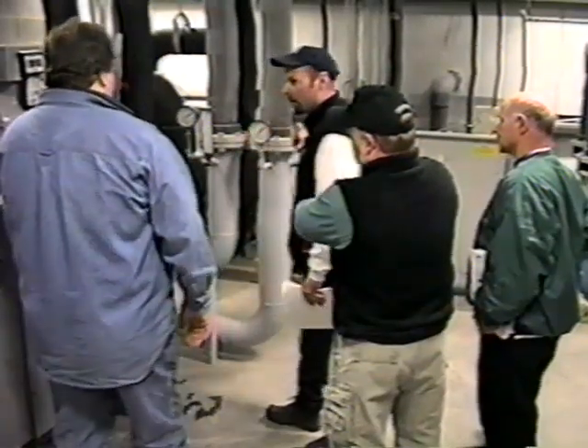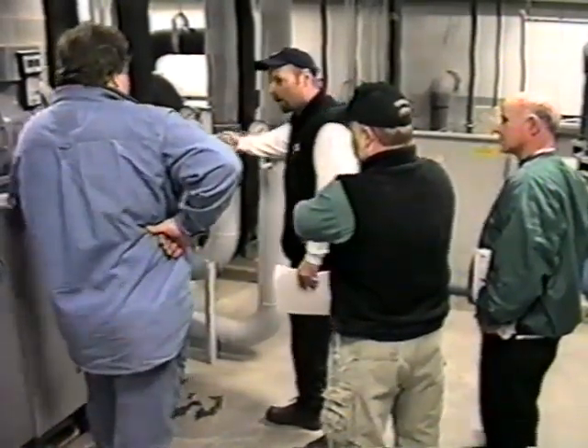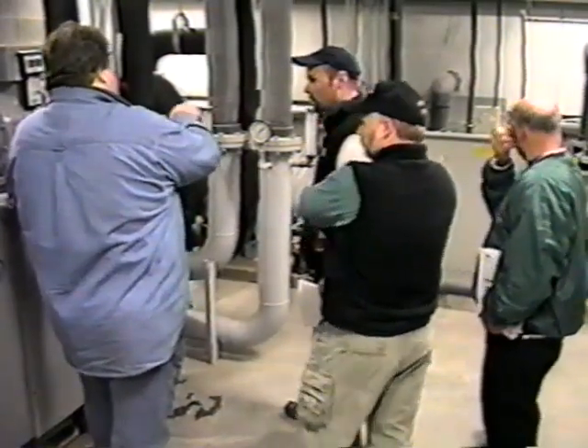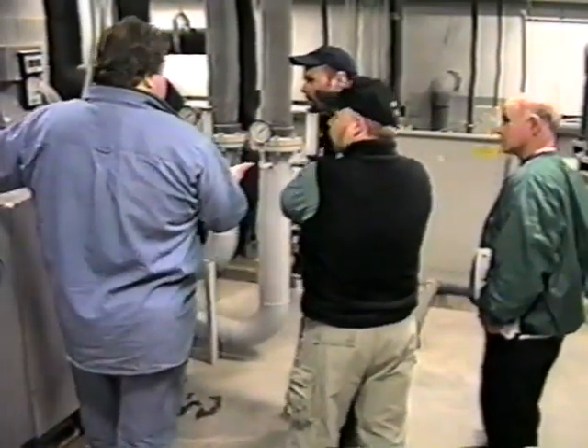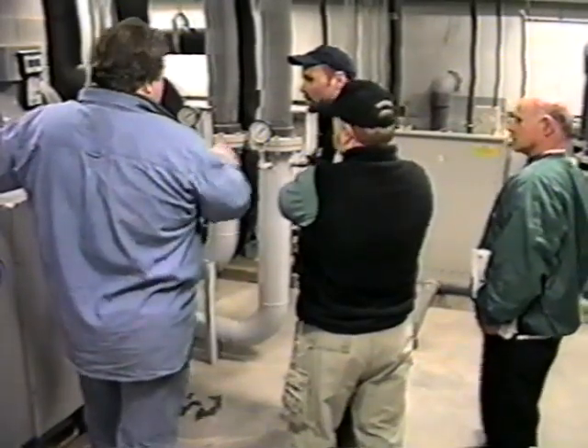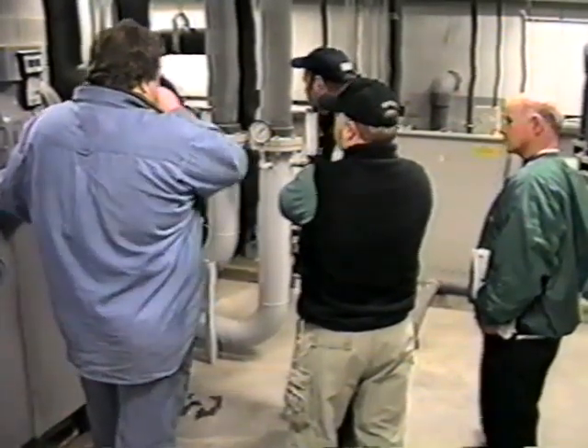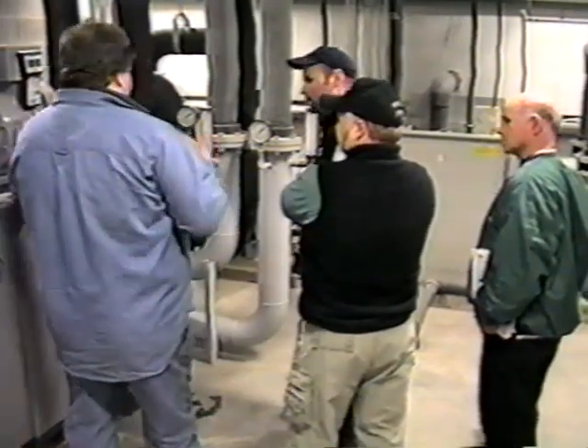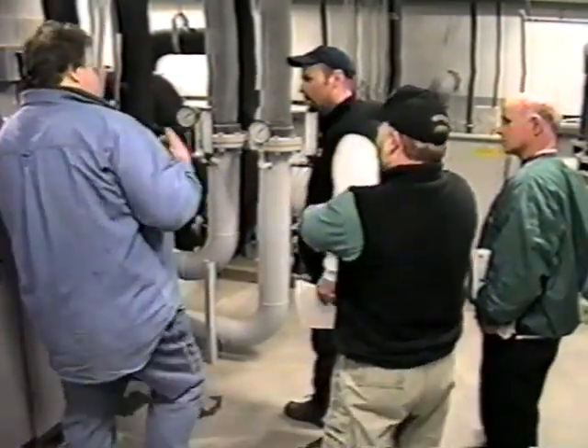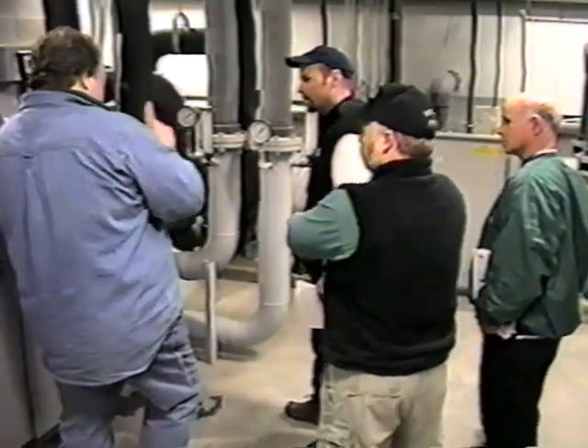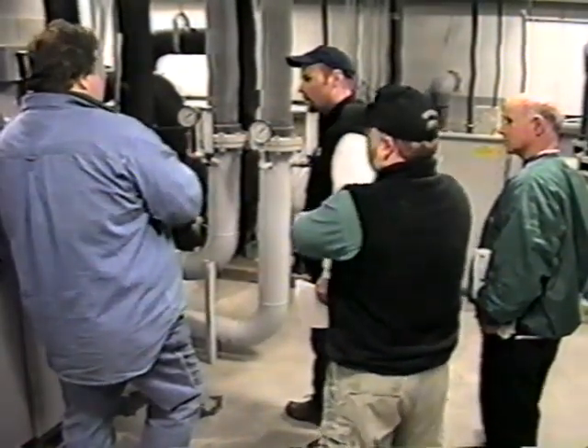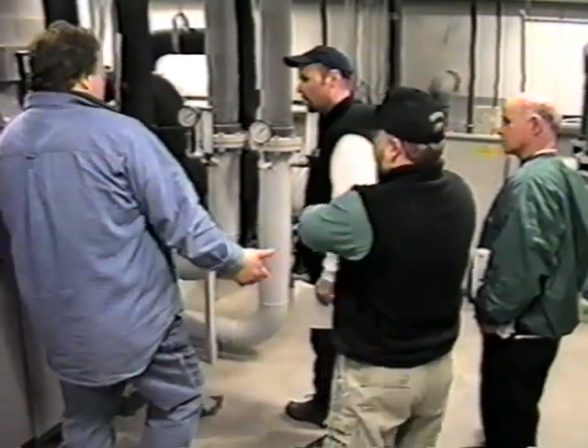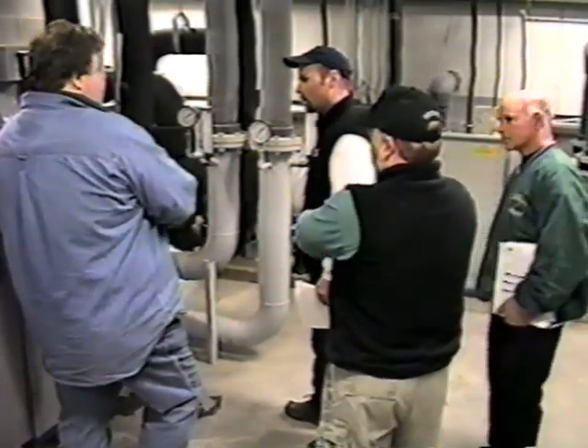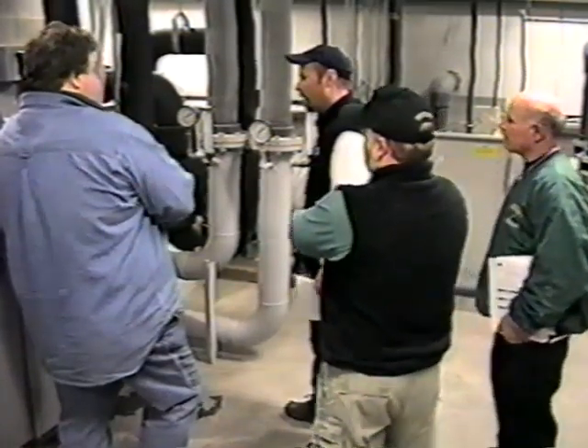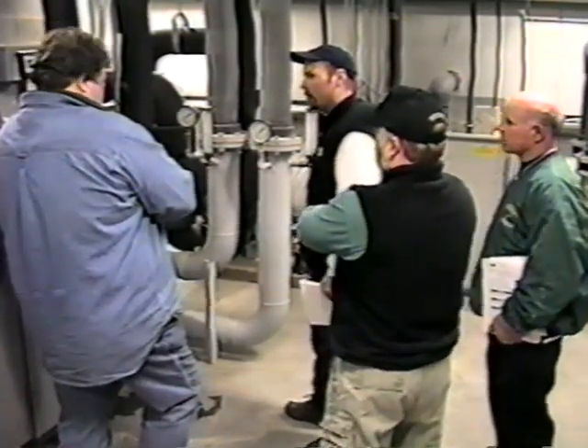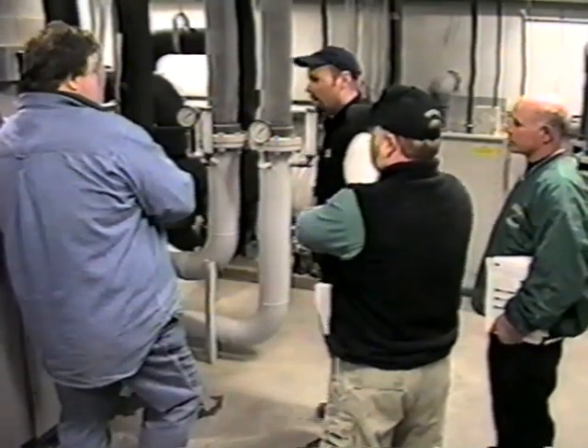Should we keep an eye on these temperatures or write any of these things down? I would. Actually, you're going to be able to get this temperature over here, which is basically what we're looking for, the sump water temperature. I don't need to know both these temperatures. That would be more for preventive maintenance, where we come in periodically and take those temperatures while the machine's running and say, geez, we got a big spread and our pressures aren't right, and maybe we're plugging up our tubes. When we have our service contract with you guys and you come in on a monthly basis, are you going to take these readings? That's when they should be looking at that stuff.